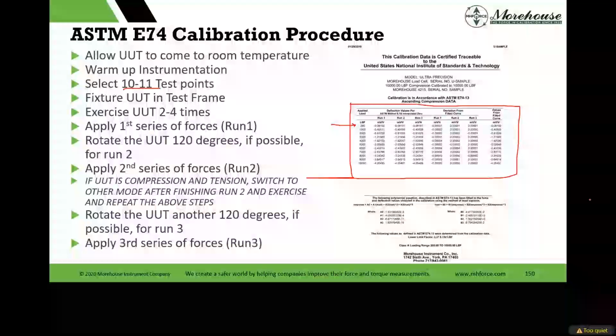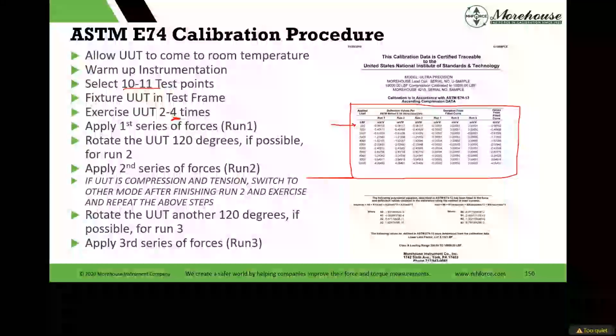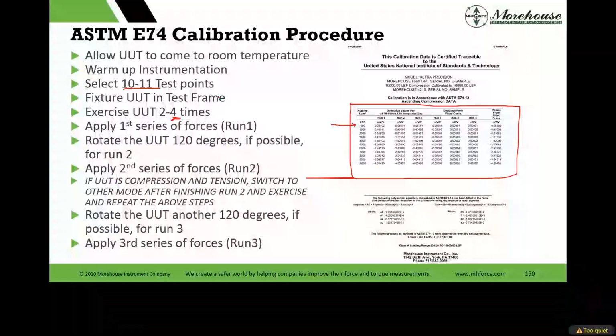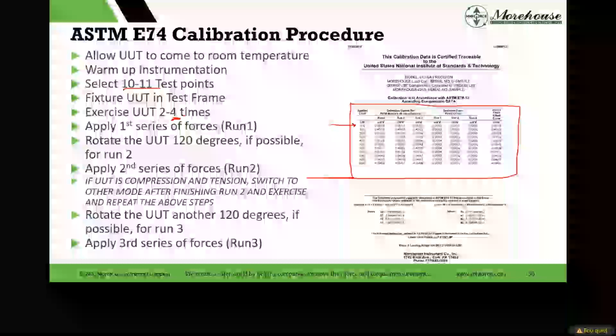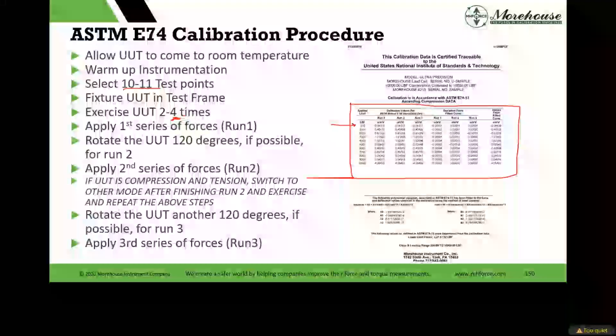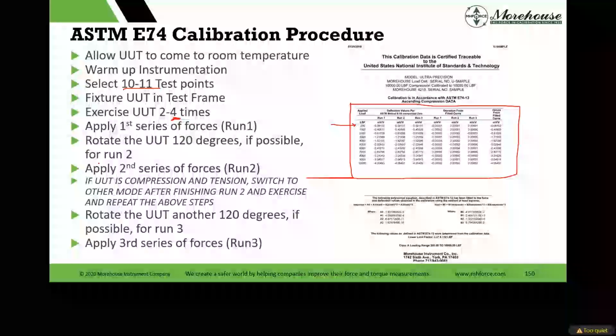So ASTM works, then you fixture the unit under test, that's UUT, in the test frame, exercise 2 to 4 times. I recommend at least 4 times. The standard says at least 2. I don't like that part. I wish it would change, because you really want that material, if it's been sitting for a while, all those molecules that are inside, you really want to get them going and excited, because if you don't do it, your first run of data is going to be much worse. So an exercise cycle on most load cells of like 4 times is not bad at all.